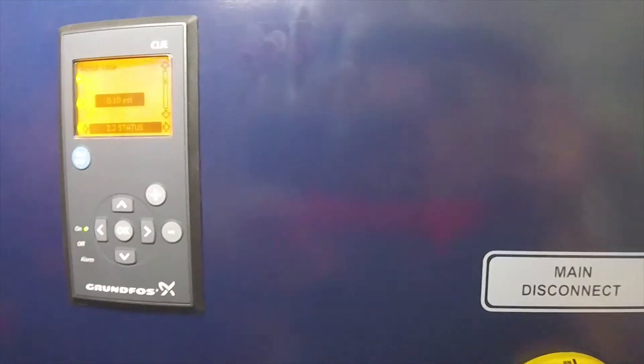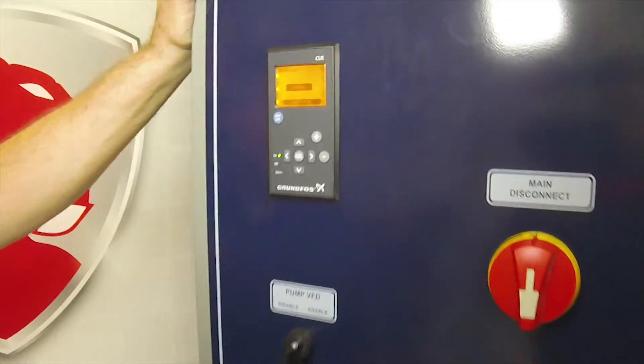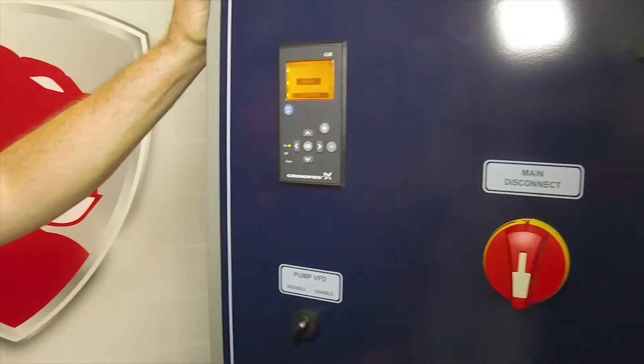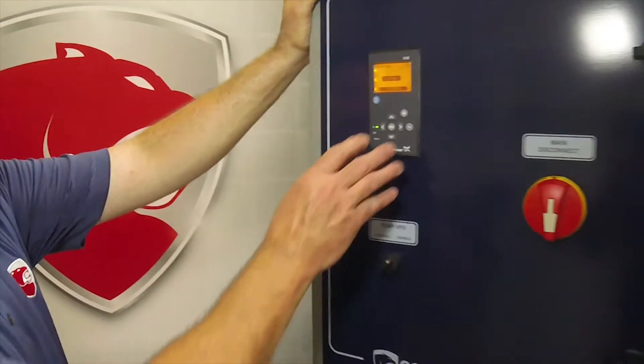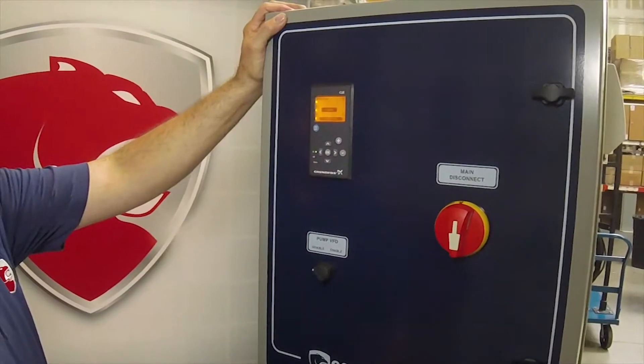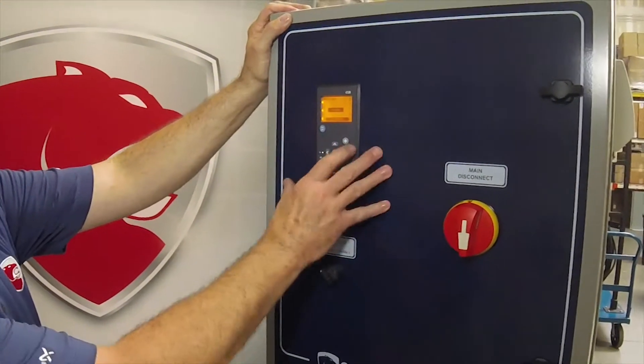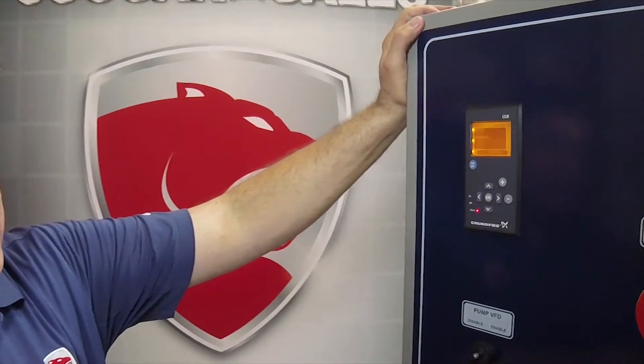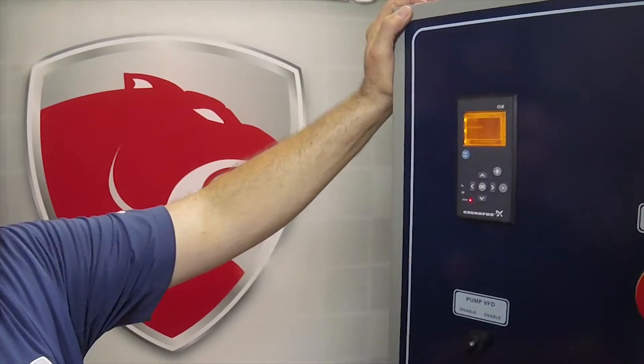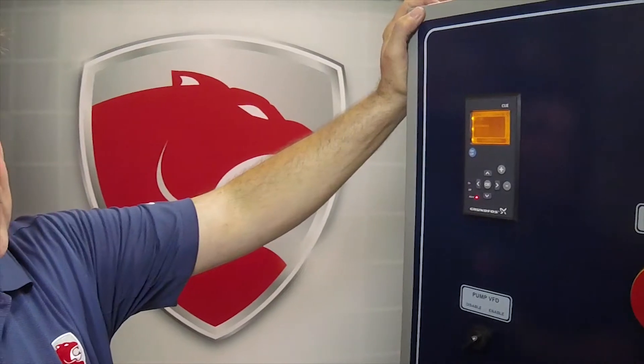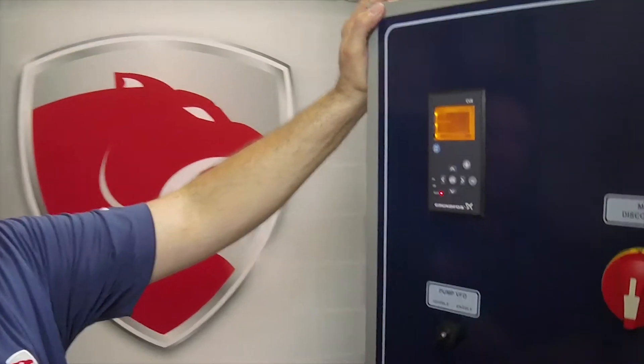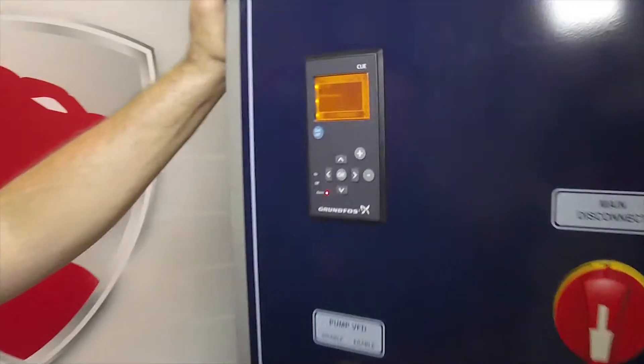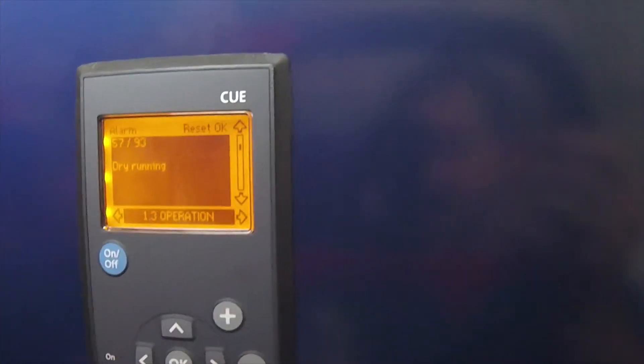That's kind of a good way to leave that so you can see what's going on. Obviously we don't have this piped up so we're showing negative pressure. Okay, we do, as I mentioned, have a pressure switch on the suction piping. If we lose city pressure, that pressure switch will actuate and give an input to the VFD.